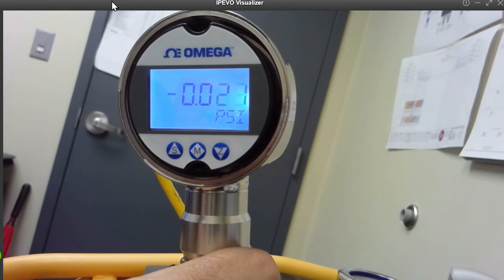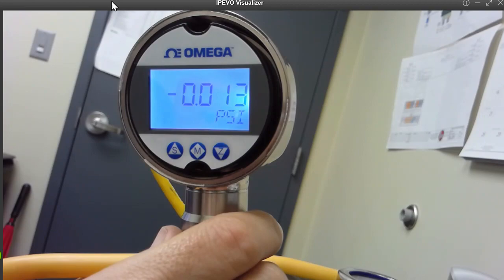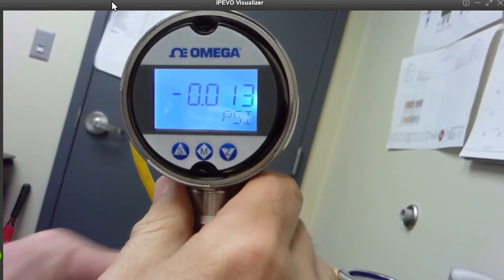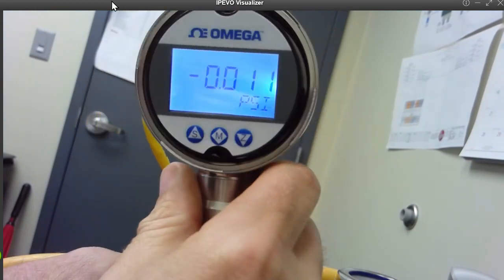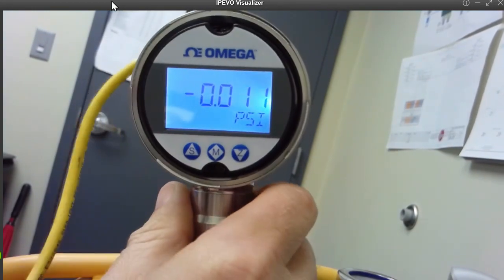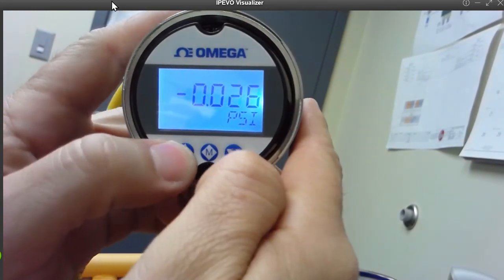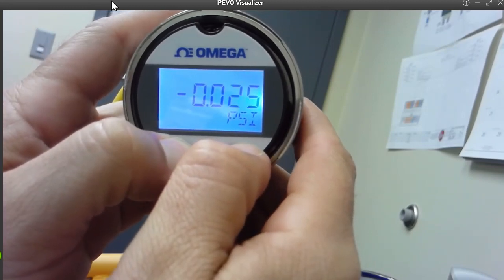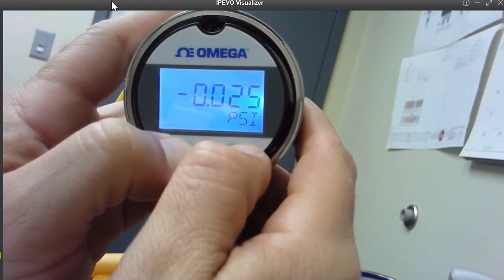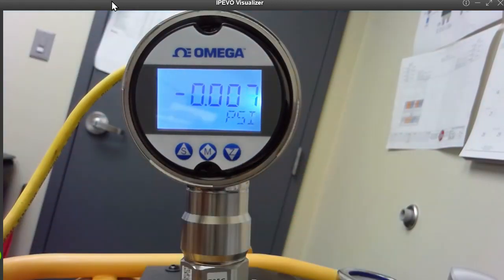So once we generated our high signal and entered it, it's now time to tare this to 0, and this will give us our low signal. You will have to make sure that this is open to atmosphere. This has to be open to atmosphere. We can't do this unless we're open to atmosphere. So we're going to hold the S and Z key for 5 seconds. And that will tare us to 0. And we should be pretty much at 0 PSI.